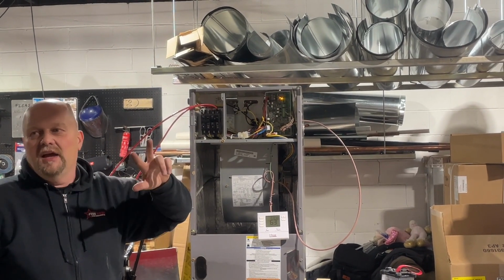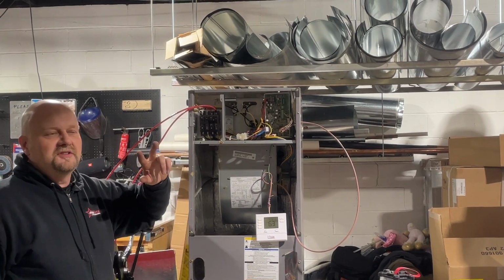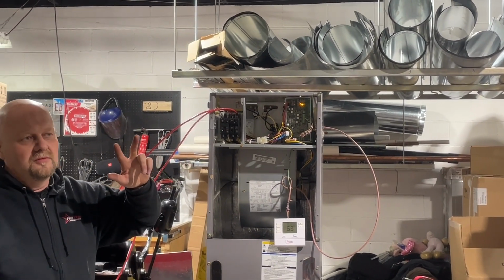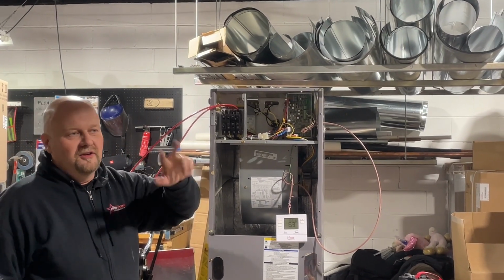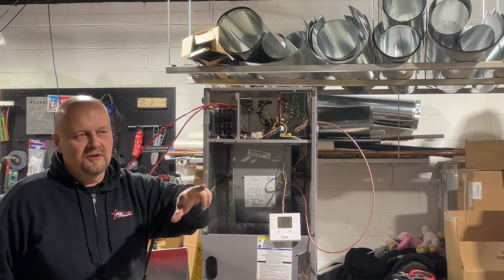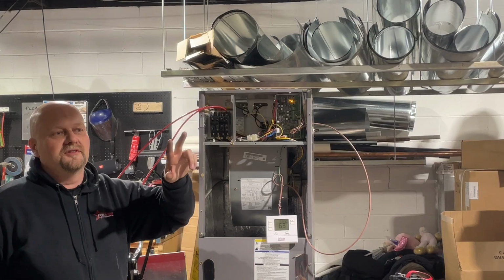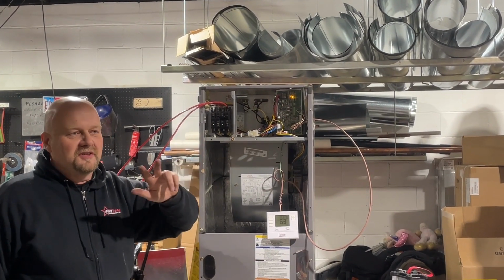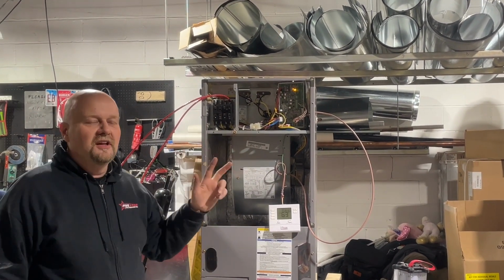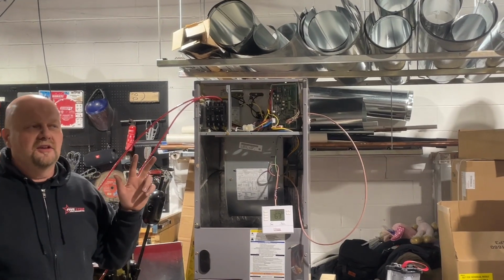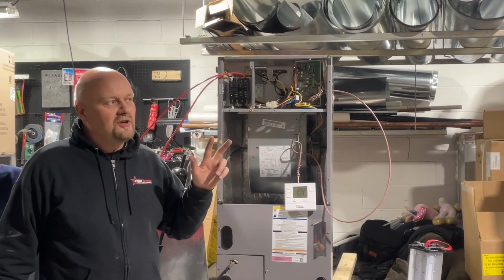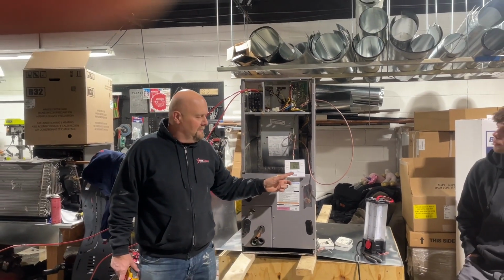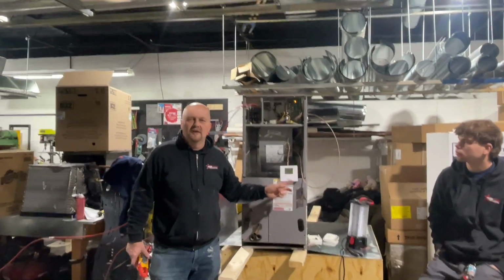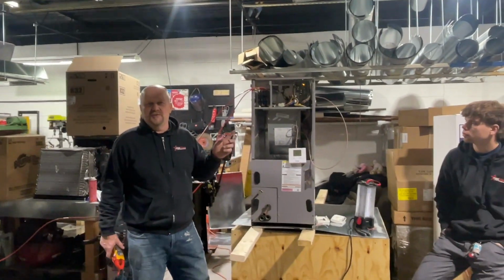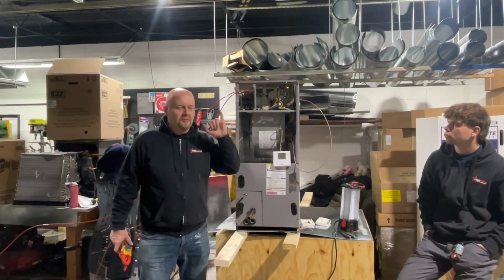So S is for stage of heat. Typically stage 1 is going to be your W1, and you're going to see that a lot on the Unico control boards. And then W2 is also S2, and S3 is a separate circuit. S3 is typically connected to an emergency output on your thermostat. So some thermostats, especially for heat pumps, will have E for emergency.